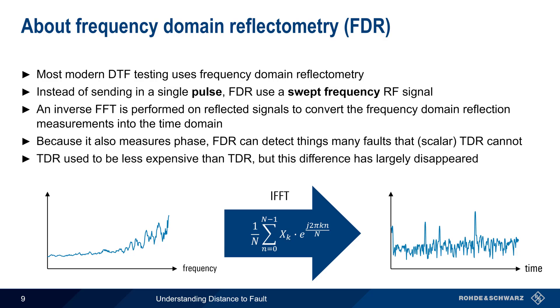Most modern DTF implementations therefore use frequency domain reflectometry. Instead of sending in a single pulse, FDR uses a swept frequency RF signal. The reflections are measured in the frequency domain, and then an inverse FFT, or Fast Fourier Transform, is performed on the reflected signals to convert this frequency domain measurement into a time domain measurement, showing return loss or VSWR as a function of time. Because FDR measures both magnitude and phase, it's more sensitive than TDR and can detect many faults which TDR could not. FDR is now the standard way of implementing distance to fault measurements in portable or field-use VNAs.